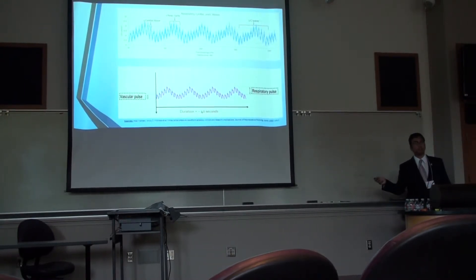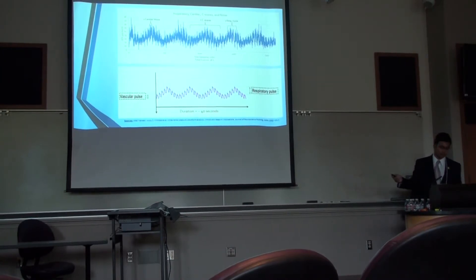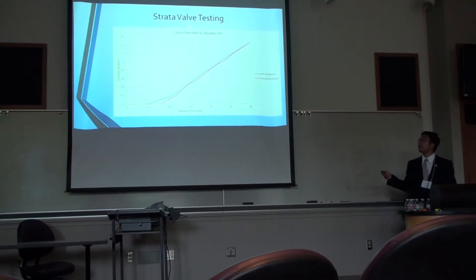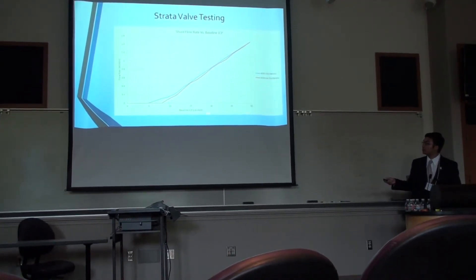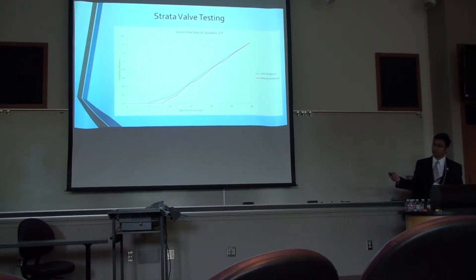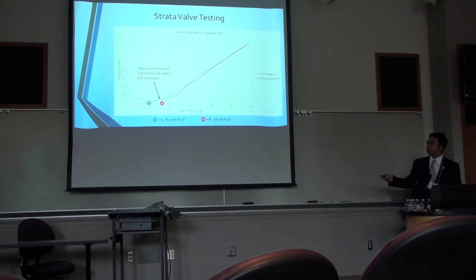I also wanted to add some randomness to the system, simply because physiology as we know it is not completely predictable. So I added some noise, and this is the final data that I got with noise input into it. The next set of tests I ran involved actually connecting one of the shunts currently on the market — a Medtronic Strata — to my testing system. I tested it under various pressures and measured the flow rate with oscillations from the speaker and without oscillations. With oscillations, I noticed that the opening pressure of this valve occurs sooner. This data really drives home the point of why a dynamic testing system is important, because it shows us how adding something more dynamic like oscillations can change valve behavior — valuable information we can take into account when programming and optimizing our smart shunt.